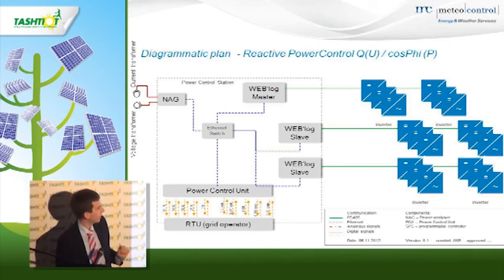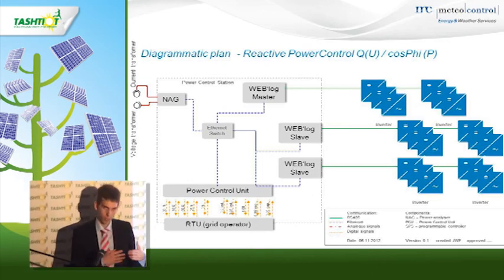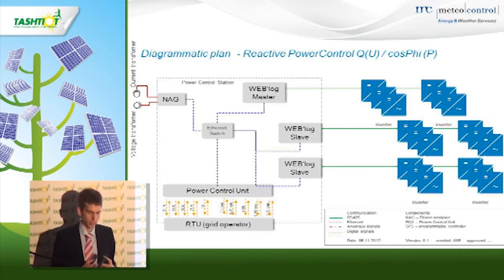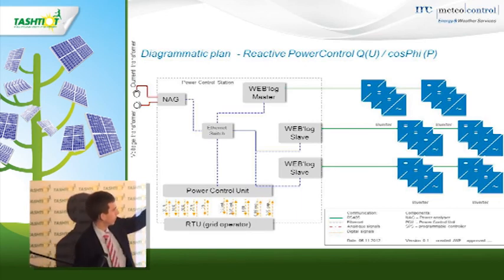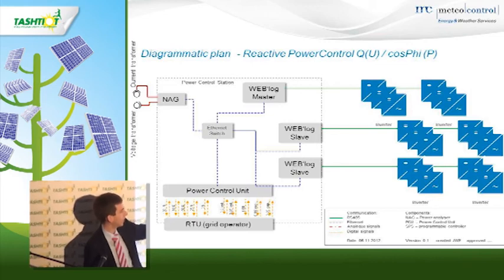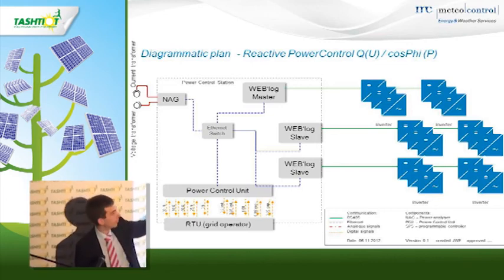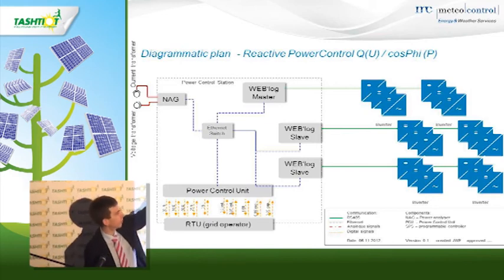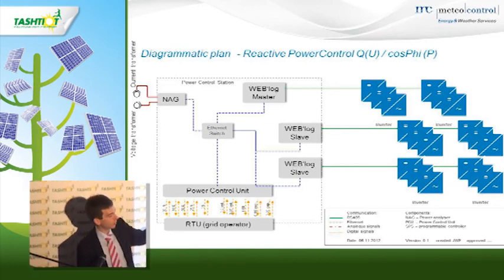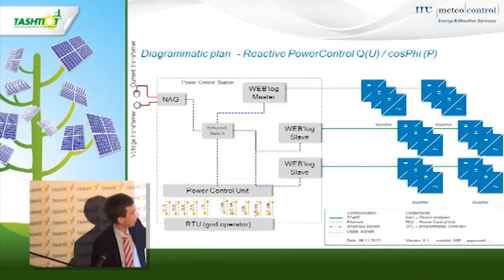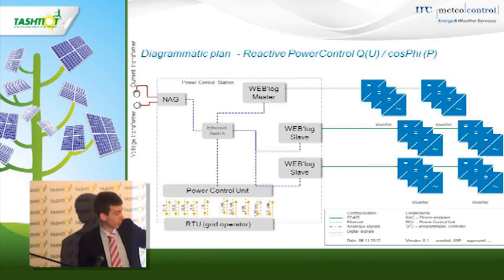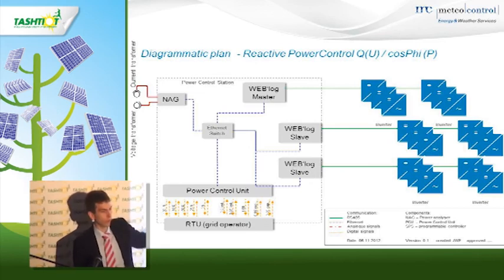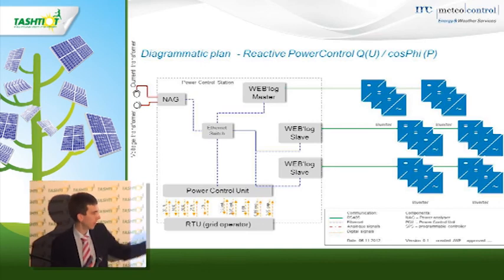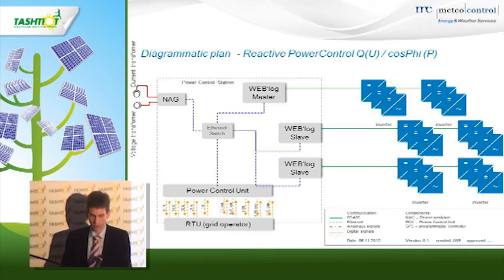And here you see an example of how the interface between the RTU and the power control unit works. So we have, for example, here 100% that the grid operator is giving to the PCU, and the PCU has to send an acknowledgement signal back to the RTU. And that's for all these 5 inputs. So if the utility gives 50% as set point for the plant, we have to give this as acknowledgement back. The same thing for the cosinus phi values.